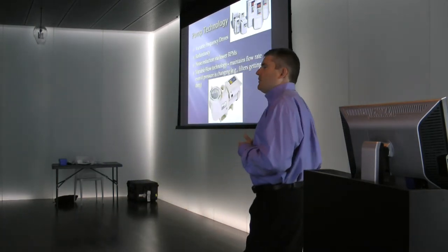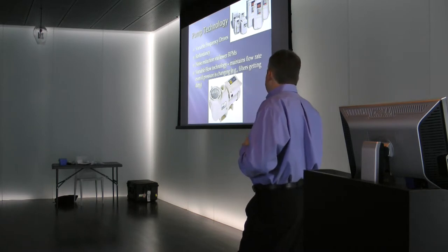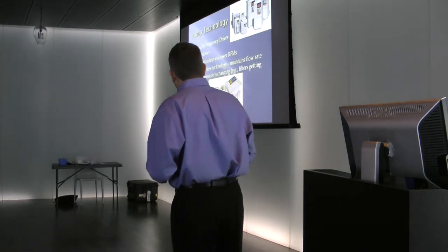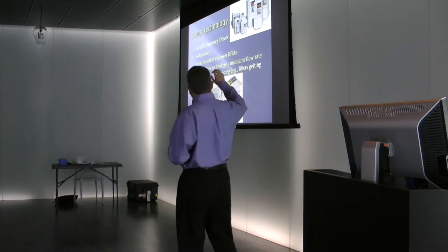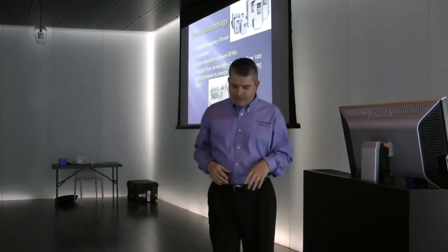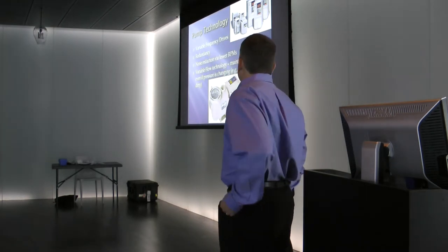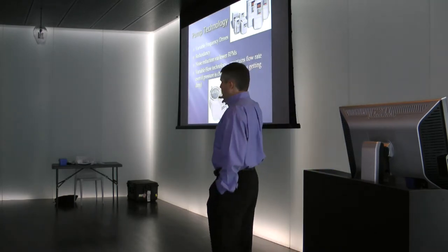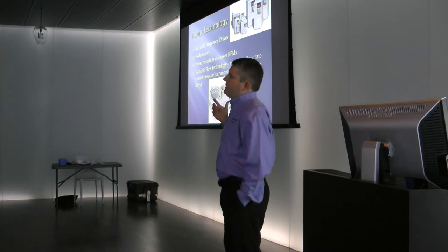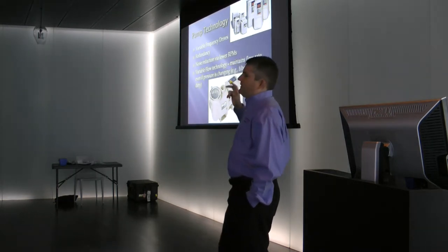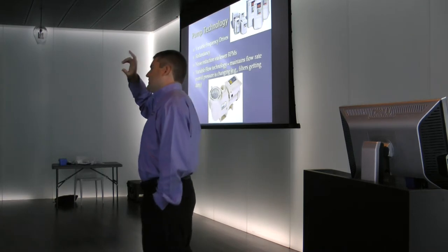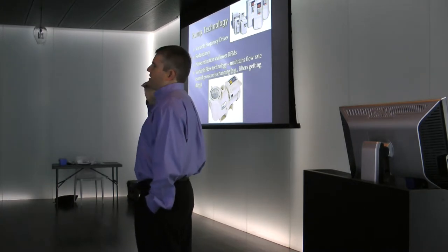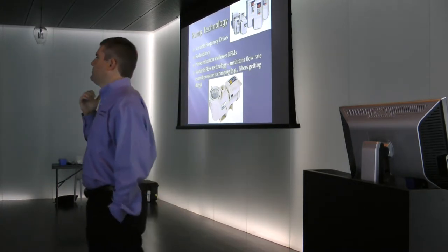When you slow things down, they get quieter, everything lasts longer, and the motors that are used are three-phase motors, which are more efficient than other motors. We've used these on all motor sizes, up to 50 horsepower. You can get variable frequency drives for any size motor. This unit here is actually a common pump in the pool industry, and the expense of variable frequency drives has come way down and sales are coming up, so the price point is really tolerable for these smaller units.